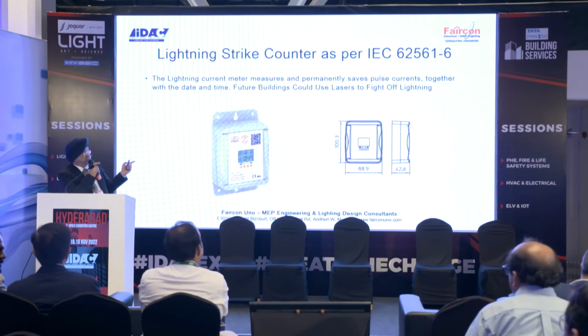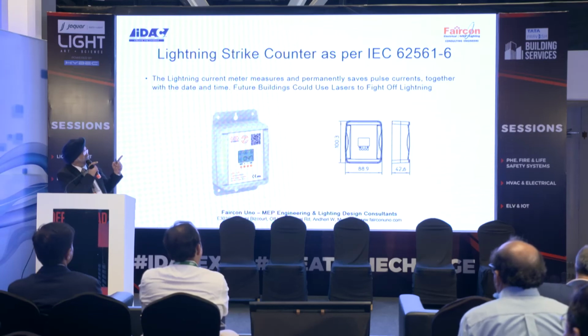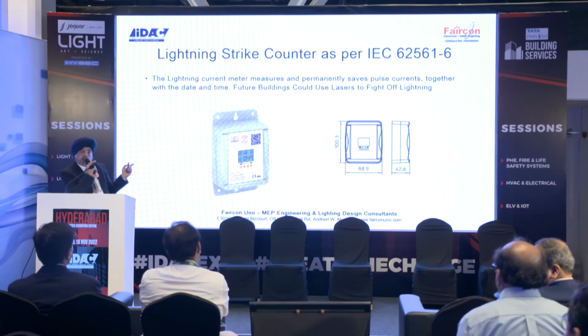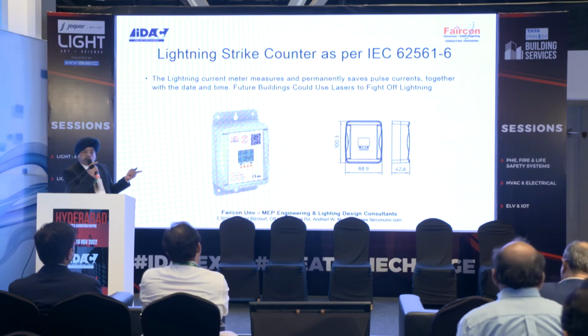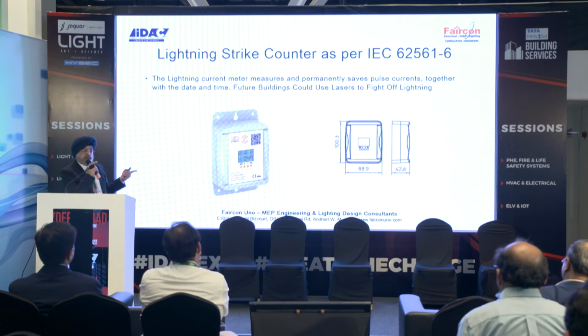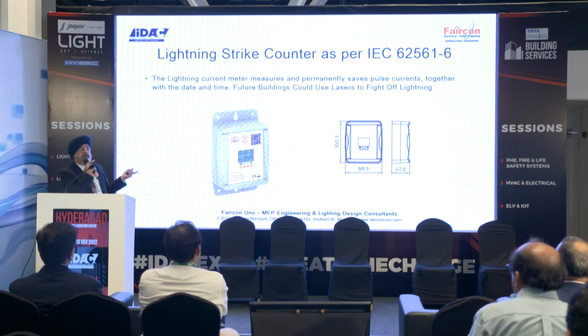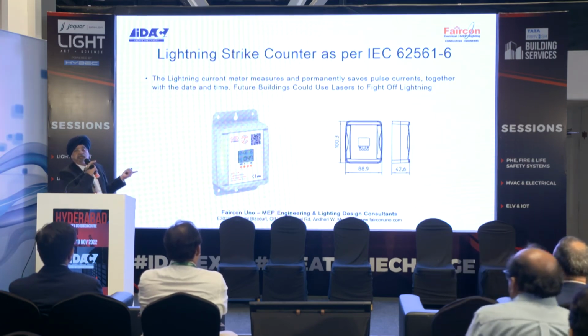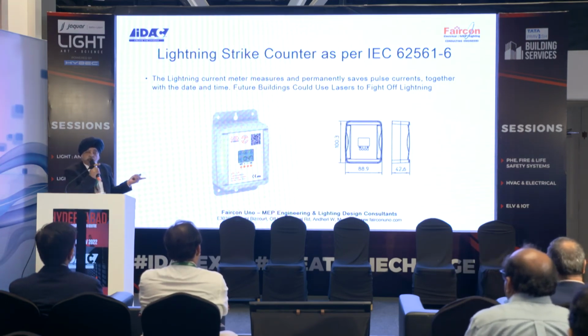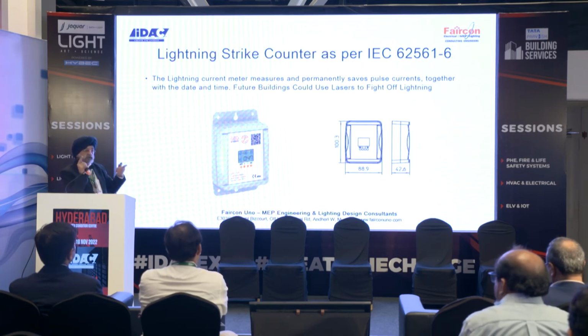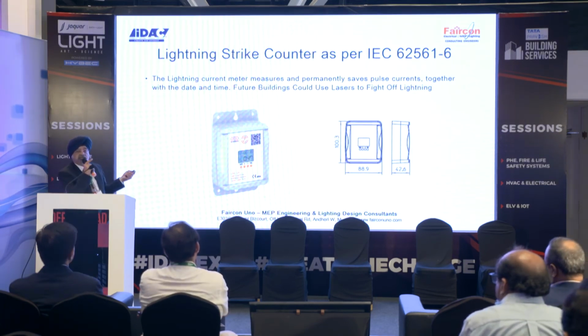This is very important. IEC 62561 tells you how to install a counter. There is no way you can make out whether your lightning protection system is working. You need to have a counter. Then only will you be able to ensure that it has done its job. Otherwise, you will have a lot of strikes going here and there, but you will not know whether you have been protected.